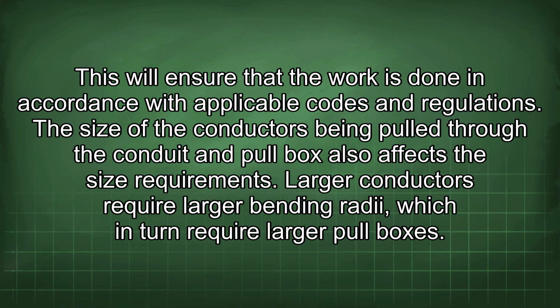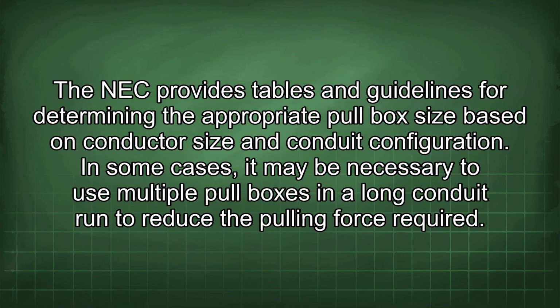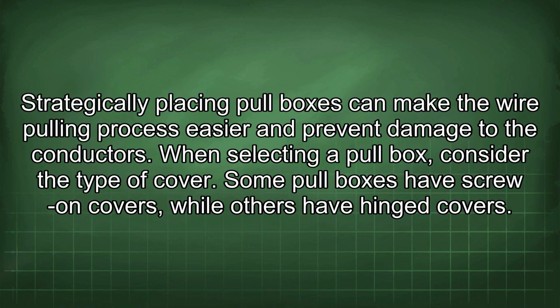The size of the conductors being pulled through the conduit and pull box also affects the size requirements. Larger conductors require larger bending radii, which in turn require larger pull boxes. The NEC provides tables and guidelines for determining the appropriate pull box size based on conductor size and conduit configuration. In some cases, it may be necessary to use multiple pull boxes in a long conduit run to reduce the pulling force required. Strategically placing pull boxes can make the wire pulling process easier and prevent damage to the conductors.